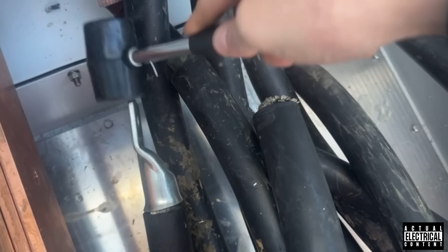Don't hit it with a hammer, otherwise you're a fucking dickhead. You'll flatten the lug out. Then we pull it up by the cable, not the lug. Go in the inspection hole and check that the strands are there, which they are.